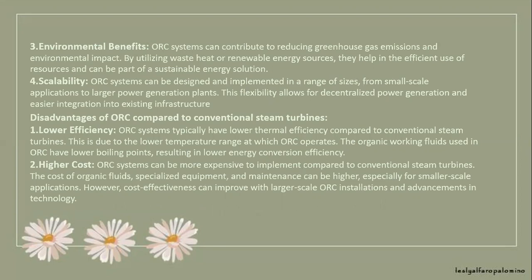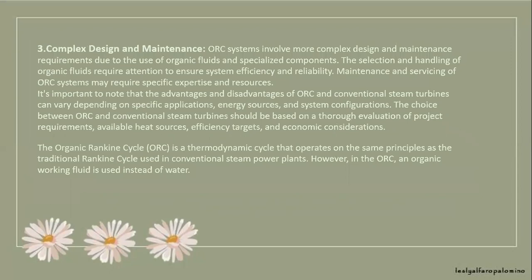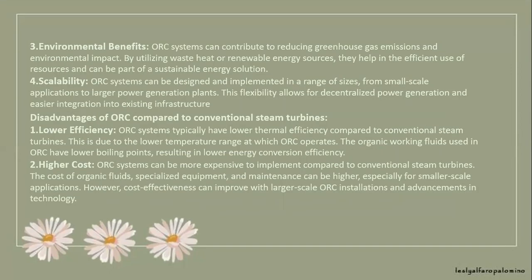Disadvantages of the Organic Rankine Cycle compared to conventional steam turbines include lower efficiency, higher cost, complex design, and maintenance. ORC systems typically have lower thermal efficiency compared to conventional steam turbines, due to the low temperature range at which the ORC operates. Organic fluids have lower boiling points, resulting in lower energy conversion efficiency. ORC systems can also be more expensive to implement compared to conventional steam turbines. The cost of organic fluids, specialized equipment, and maintenance can be higher, especially for smaller-scale applications. However, cost-effectiveness can improve with larger-scale ORC installations and improvements in technology.